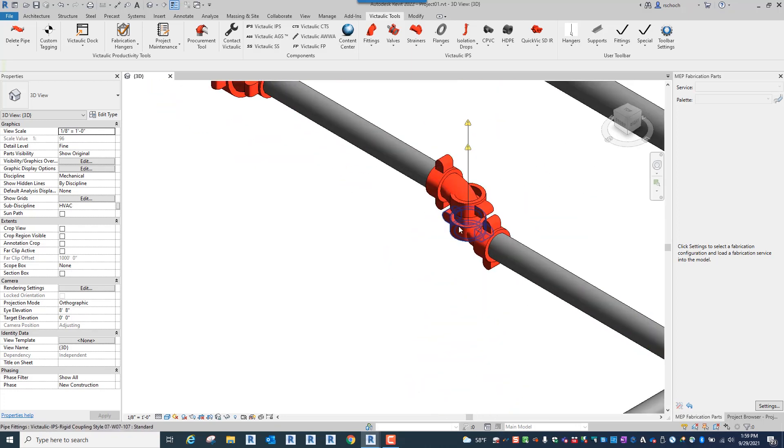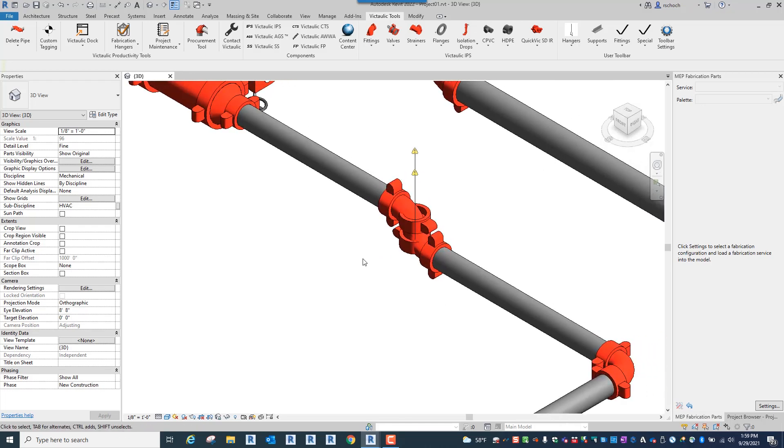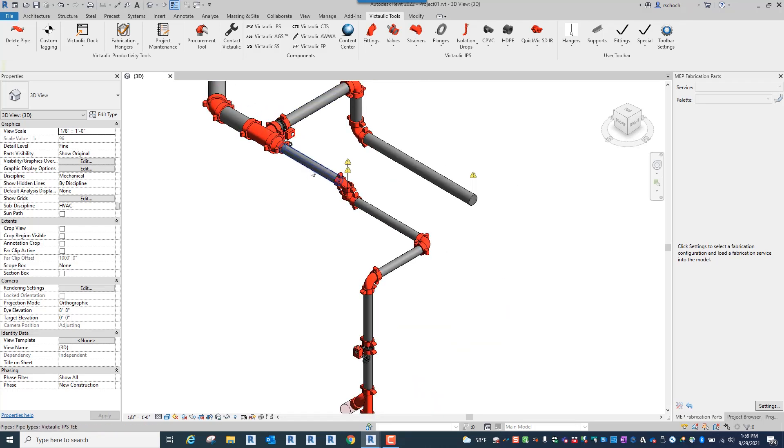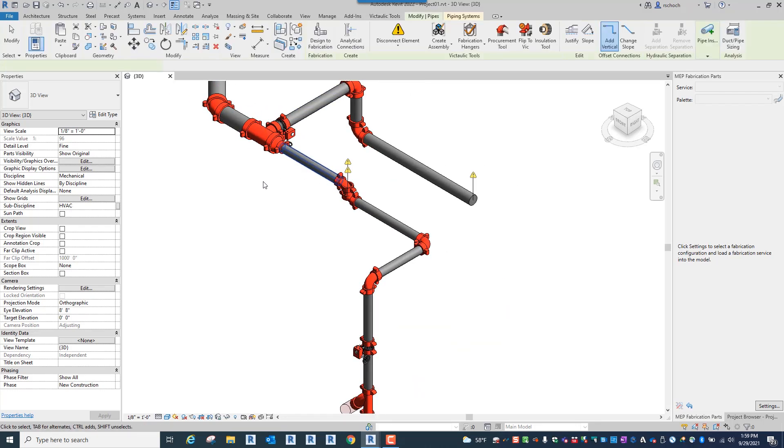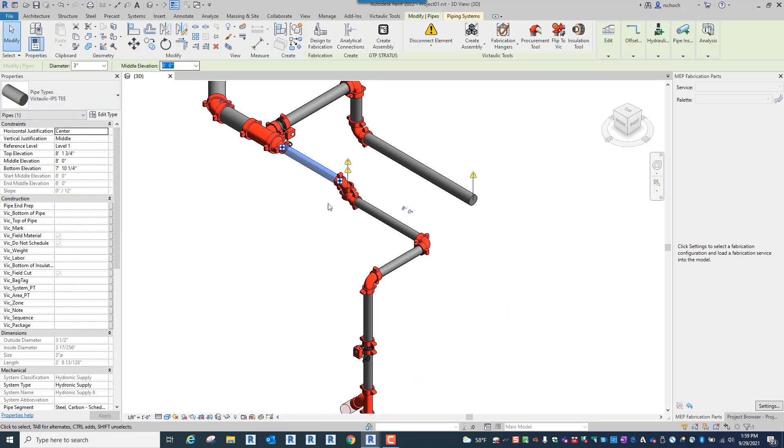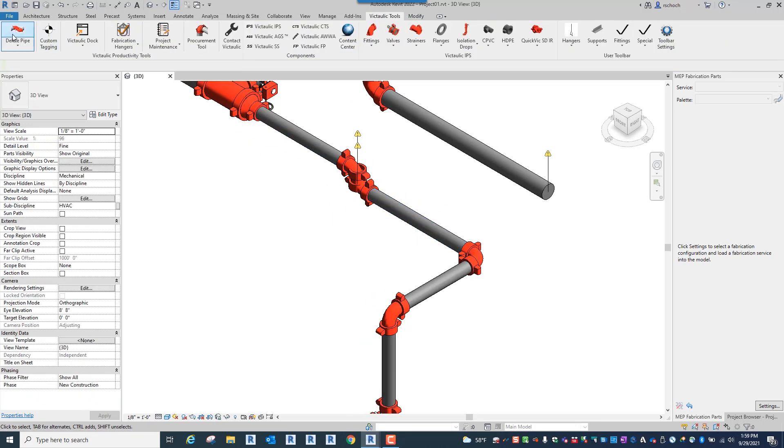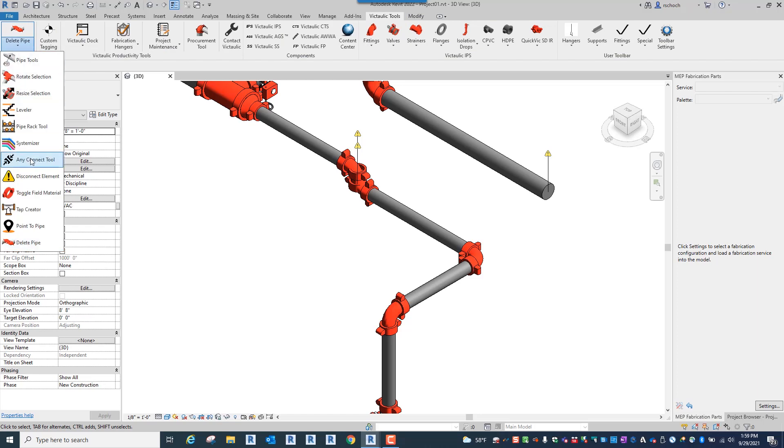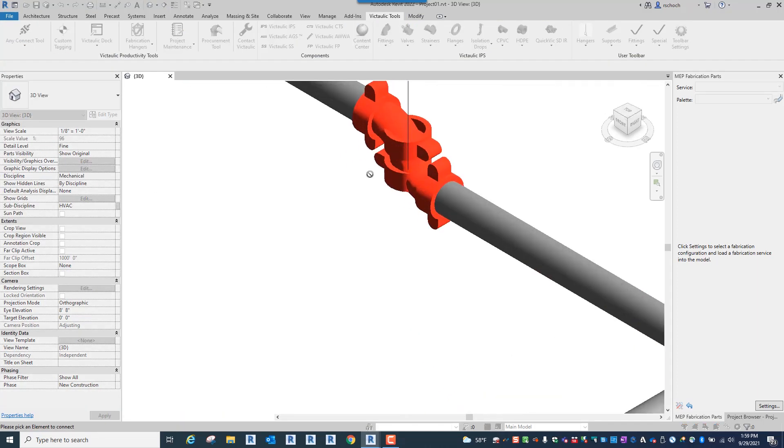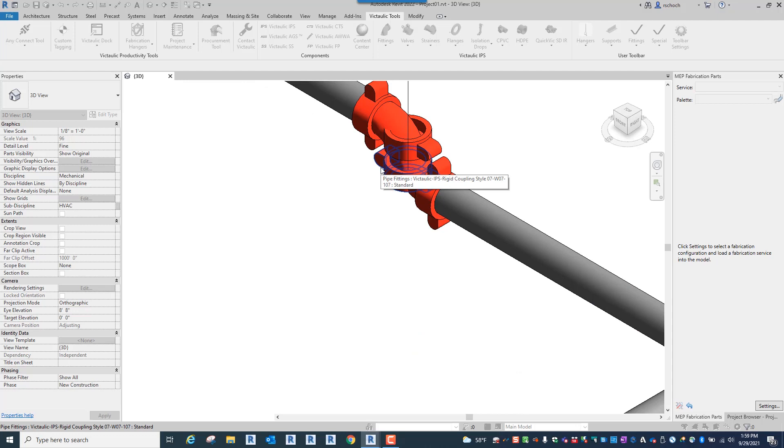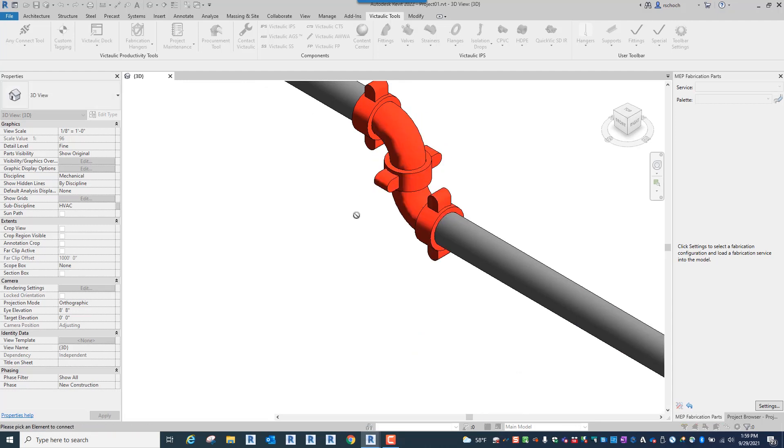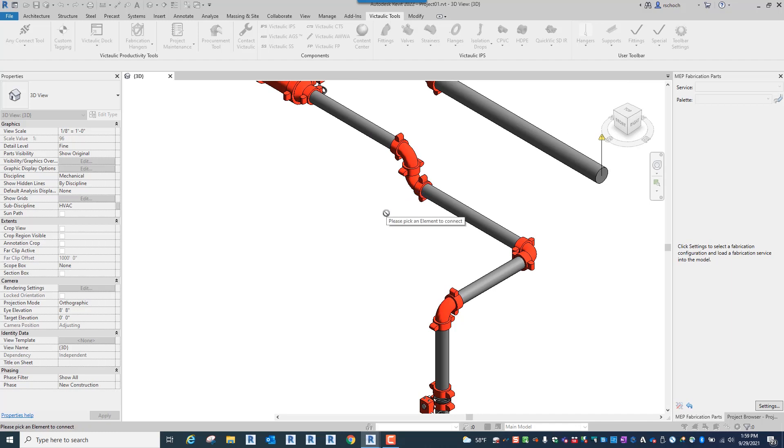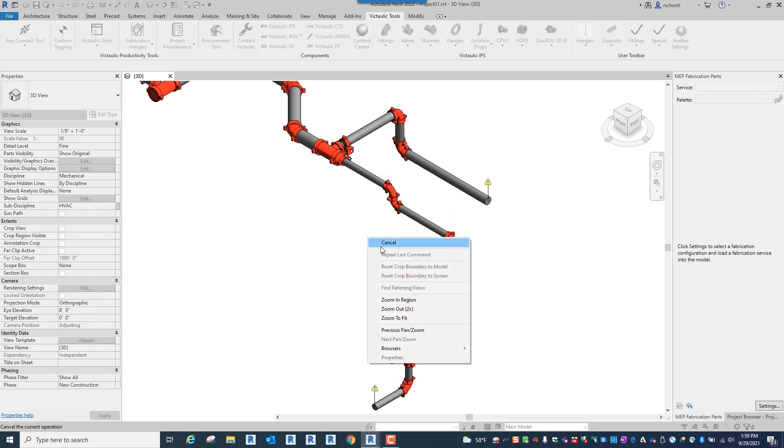So you can see here we have a disconnect. I have my disconnects turned on. A neat trick to fix this—now I need to decide which piece of pipe set to correct elevation. So I want to keep the main elevation consistent. So if I take a look at this, this is at eight foot. This one here is at seven seven. I'm going to make this fitting to fitting. We have a tool for that called AnyConnect. I can select this coupling which is from the top elbow and this coupling. And you're going to see it pulls those two pieces fitting to fitting. So a lot of our other tools combined with the Flip2Vic are definitely going to speed up your process and your workflow.